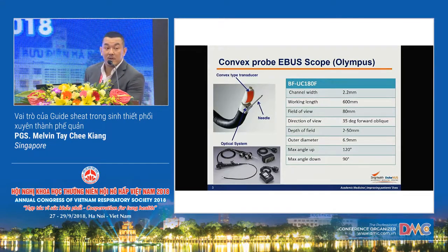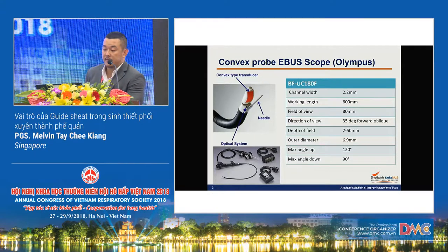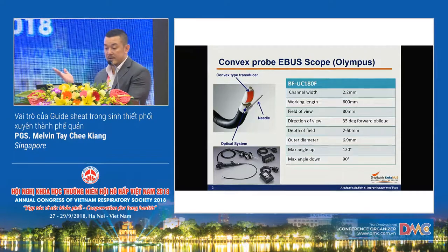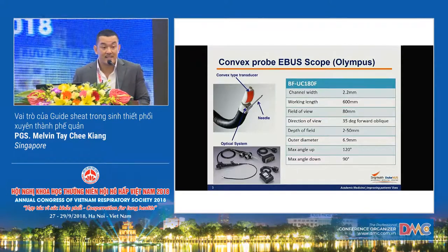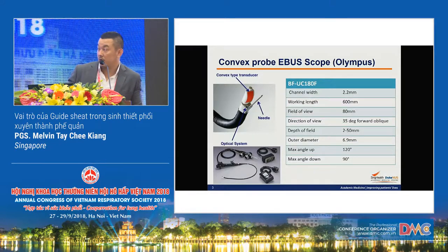The convex probe EBUS scope from Olympus features a convex-type transducer which transduces the ultrasound image, an optical system, and a needle. The channel width is about 2.2 mm and the outer diameter is about 6.9 mm. It is important to remember that the direction of field is about 35 degrees forward oblique, which is why when using the EBUS scope you should not see the entire lumen normally encountered during flexible bronchoscopy.